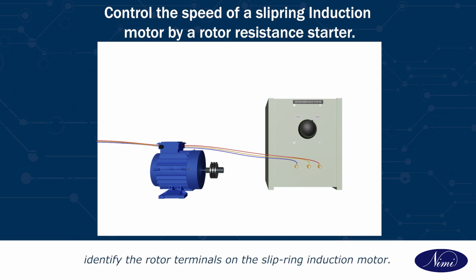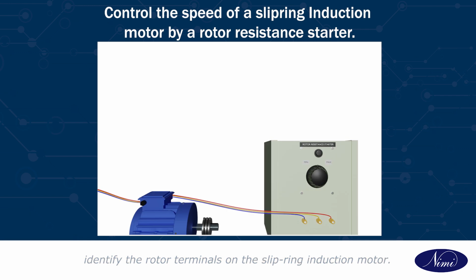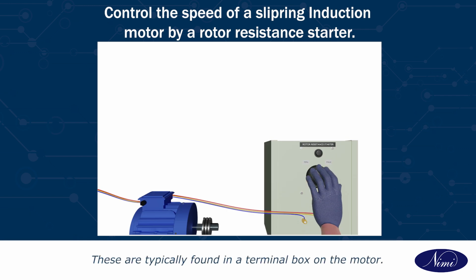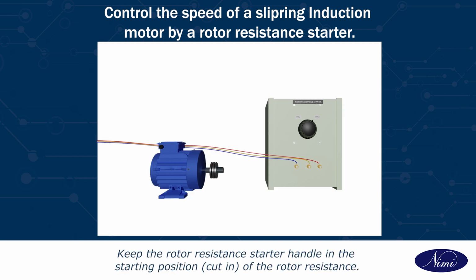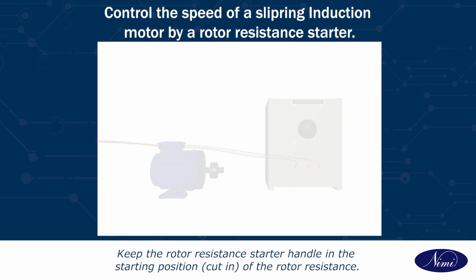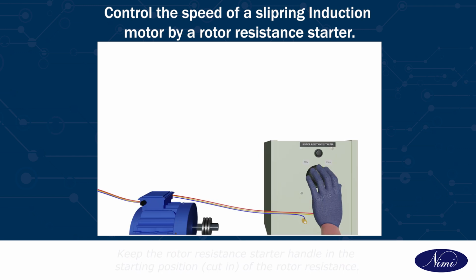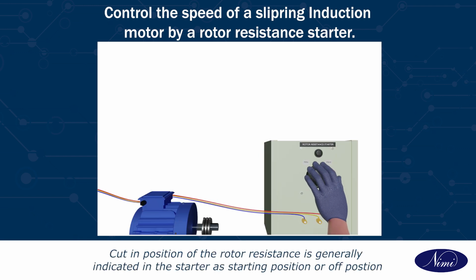Identify the rotor terminals on the slip ring induction motor. These are typically found in a terminal box on the motor. Connect the resistors of the rotor resistance starter to the rotor terminals of a motor. Keep the rotor resistance starter handle in the starting position. Cut-in of the rotor resistance. Cut-in position of the rotor resistance is generally indicated in the starter as starting position or off position.